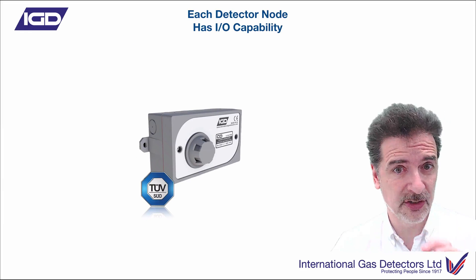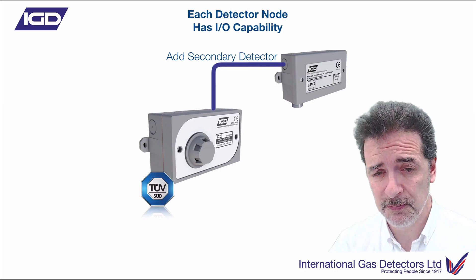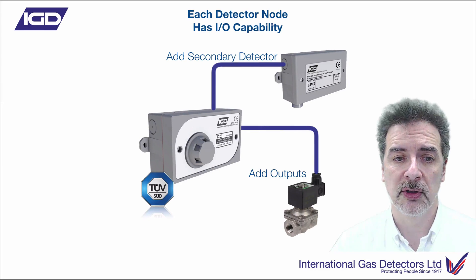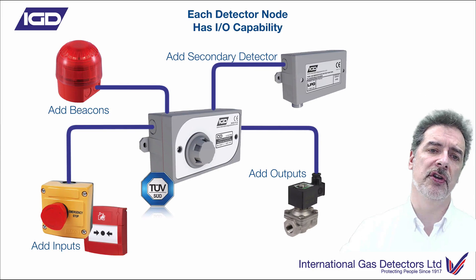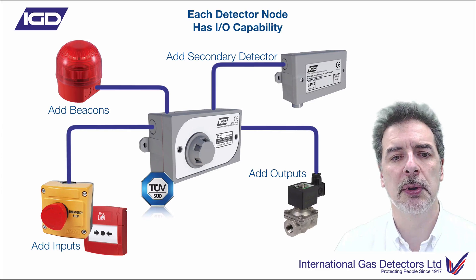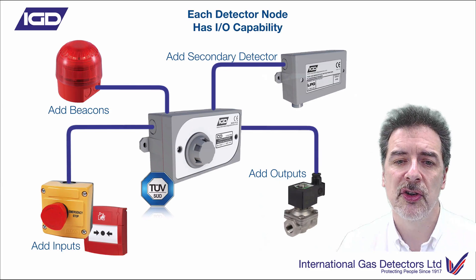We're talking about detectors — or detector nodes as we've started calling them — because each one of these detectors now has multi-IO capability. So if I've installed a detector and I want to add an additional device, perhaps a secondary detector, perhaps I want to use a relay output to control a solenoid valve or interface to a fire alarm panel, or maybe I want to add inputs in the form of slam switches or break glasses, or add a beacon sounder — I can do all of those on the detector node. You've got seven options on the detector node to add that kind of capability. These are really, really flexible. You can literally put your cable highway loop in and decide afterwards how you're going to connect your beacon sounder or relay — just connect it to the nearest detector node. A nice and efficient way of doing it.